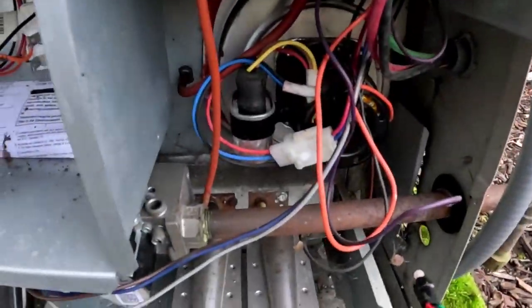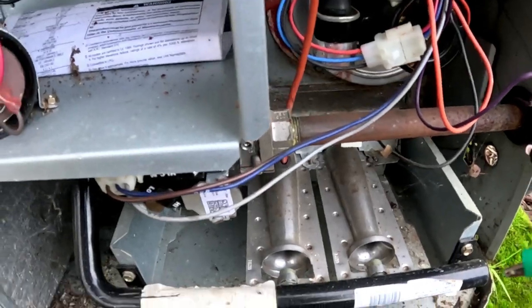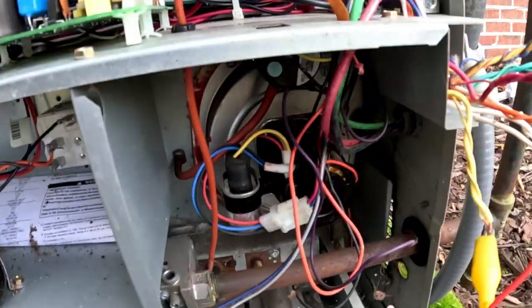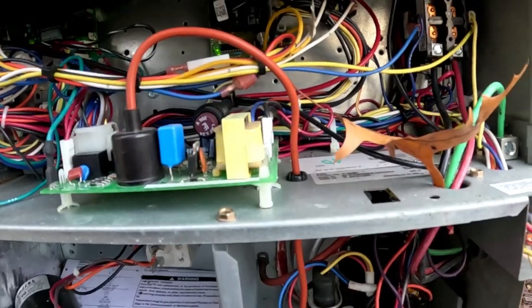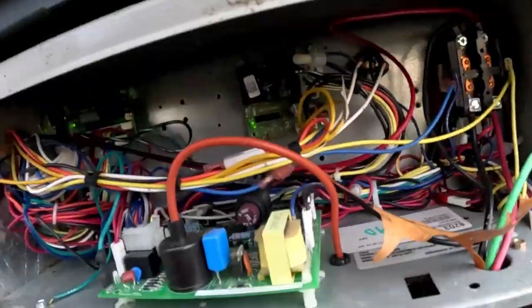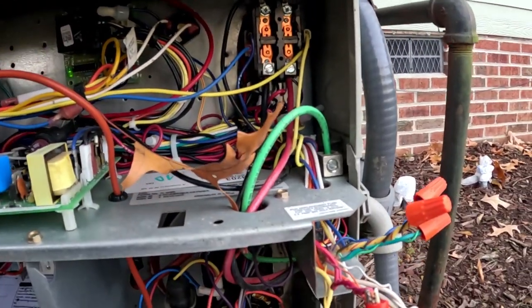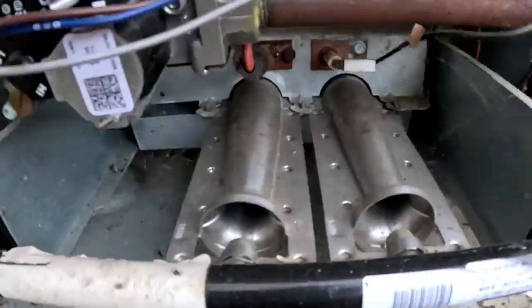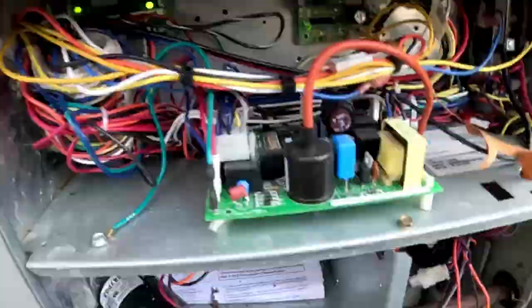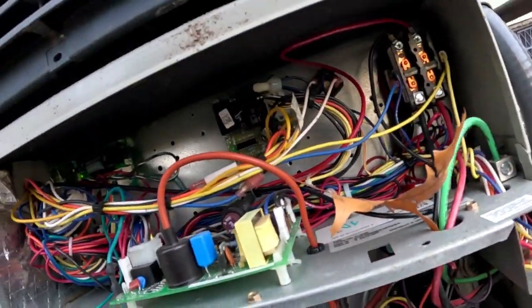Now the draft motor is coming on. This thing's going to fire off and run the furnace and the heat pump at the same time, which means you're going to overheat it — limit switches and all that stuff. You'd think Trane would be smart enough to know that when you get a call for the gas furnace to run, it would shut the compressor off. But Trane's stupid.